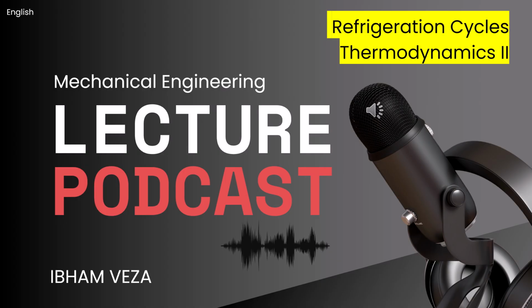A flash chamber, what does that do? It's basically a tank where some of the liquid refrigerant coming from the condenser is allowed to flash evaporate at an intermediate pressure. This cools down the remaining liquid refrigerant before it goes to the main evaporator. The flash vapor is often rerouted to the inlet of the second stage compressor. And that helps. How? It reduces the total work the compressors have to do. It's a form of intercooling and regeneration within the cycle itself. It can give a really nice bump in COP compared to single-stage compression for the same conditions. Maybe boost a COP from, say, 4 to almost 4.5 in some cases.